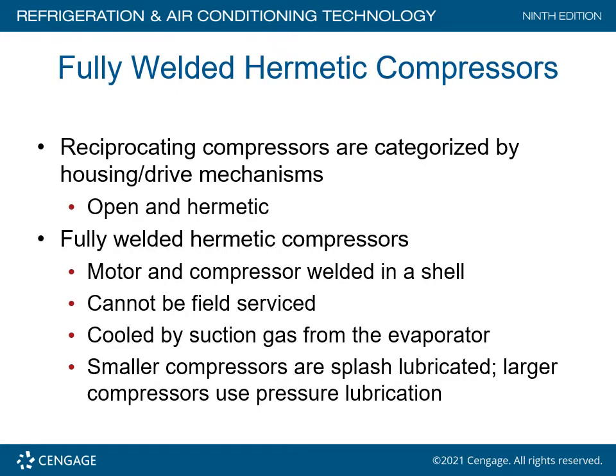Reciprocating compressors are categorized by housing and drive mechanisms — open and hermetic. Fully welded hermetic compressors have the motor and compressor welded into the shell. They cannot be field serviced; they either work or they don't. They are cooled by suction gas from the evaporator. Smaller compressors are splash lubricated; larger compressors utilize an oil pump, referred to as pressure lubrication.